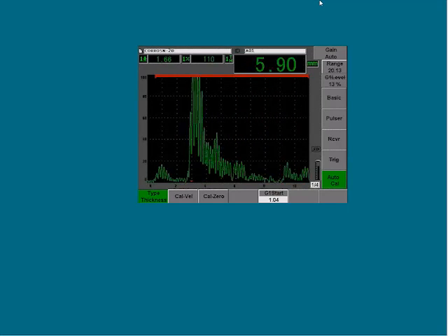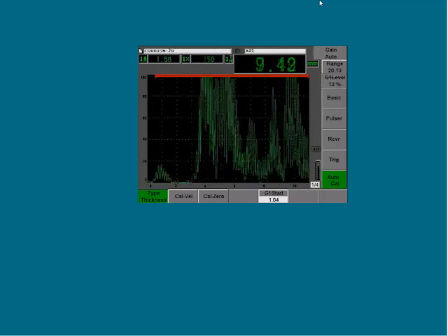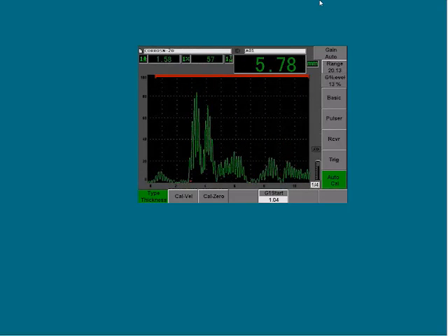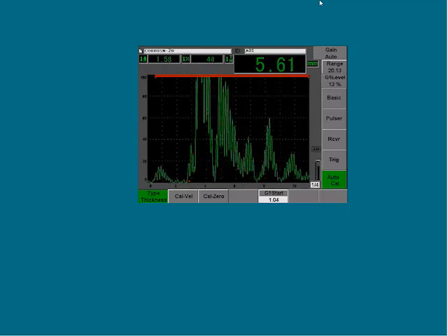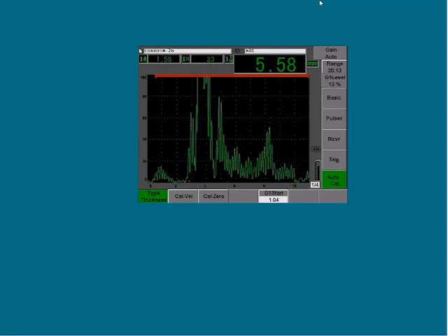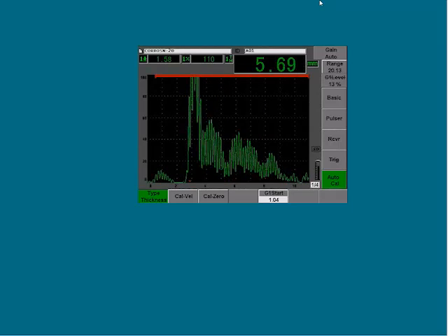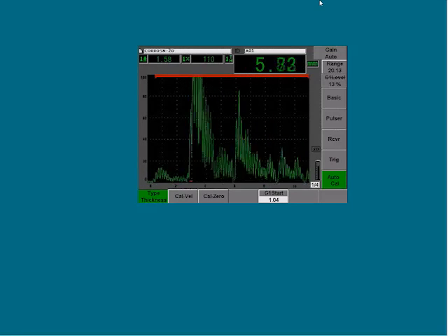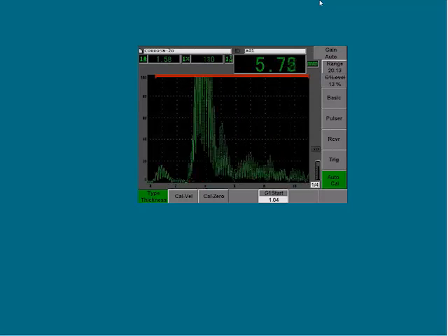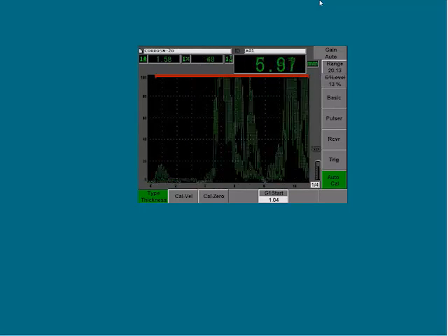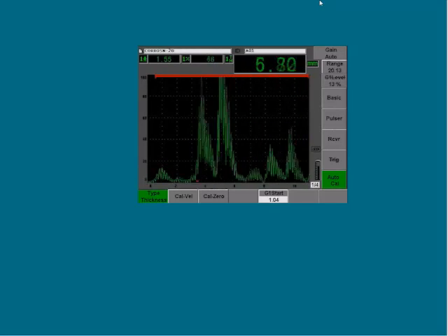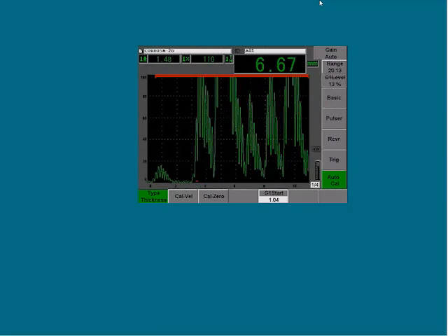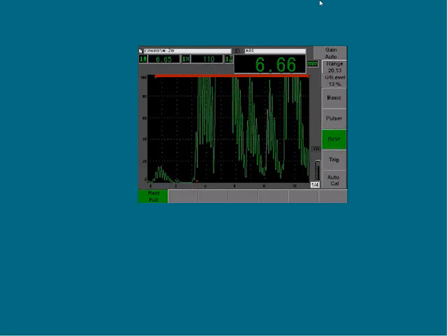And if I go ahead and start looking at an actual corroded sample, you can see that on the bottom here we have a little measurement caret that shows me where I'm making my actual measurement. The gate level is not required for the operator to manipulate. This is not something that an operator needs to worry about anymore because we're using the threshold and zero cross detection algorithm. So this really enhances the life of the operator quite a bit, and you can make fast and repeatable measurements. You can review the pulser settings, but from this menu you can't actually make adjustments.